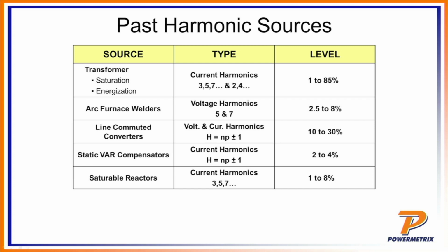If we look at past harmonic sources, in other words, over the last 100 years, what sort of things cause harmonics? Most notably, transformers. A transformer, of course, is designed to accommodate a certain amount of power. If you exceed the power rating on a transformer, it will go into saturation, meaning that basically I can't get any more power out of this transformer. A lot of times it will end up truncating the sine wave, and so it will go from a nice sinusoidal waveform to looking more like a square waveform. And as we saw earlier, that can add quite a bit of harmonic energy. And so the output level could be anywhere from 1 to 85%.